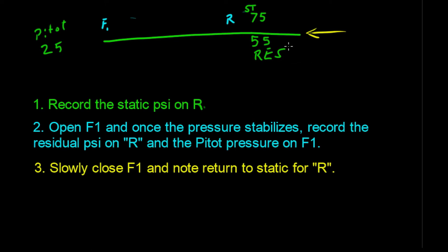All right, after that, you slowly close this hydrant, and then they'll just watch this and make sure it returns to normal static pressure. Everything's good. Allow this hydrant time to drain before you put the caps on, because if you put the caps on and tighten them down before this hydrant drains, it won't allow air to come in and allow the water to drain out of the hydrant.